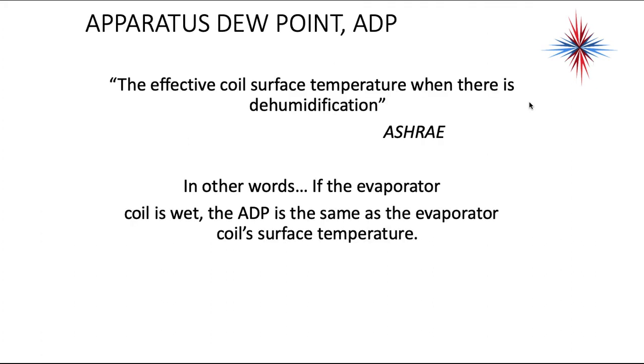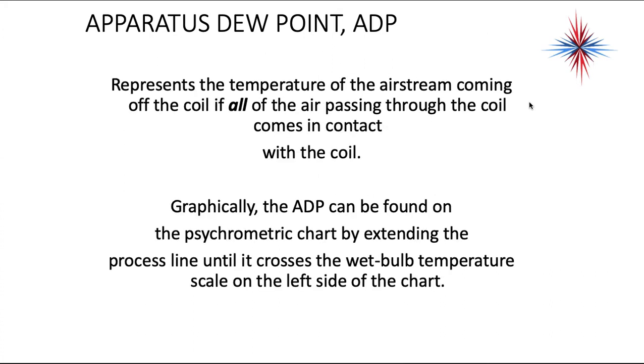Let's first talk about apparatus dew point temperature. ASHRAE says the effective coil surface temperature when there's dehumidification is the ADP. In other words, if the evaporator coil is wet, the ADP is the same as the evaporator coil surface temperature. Coil is wet means it's at its dew point, so the evaporator coil surface temperature is the ADP.